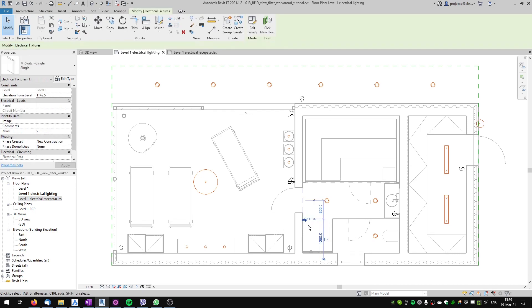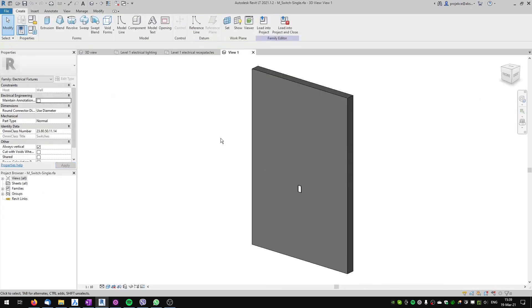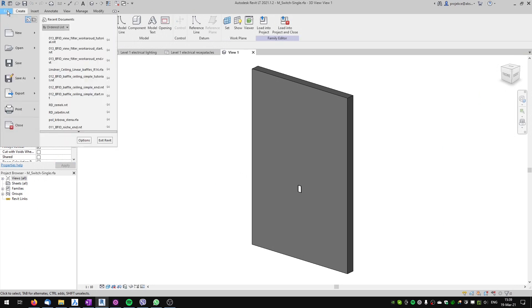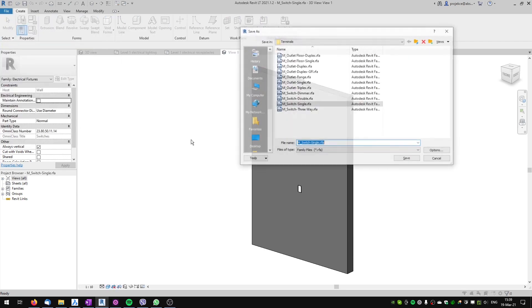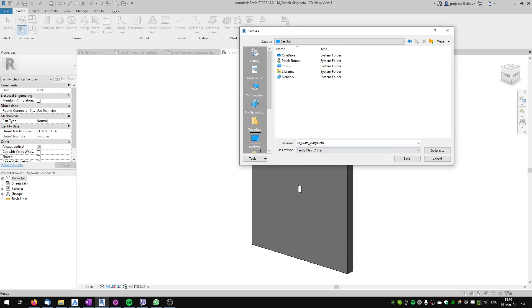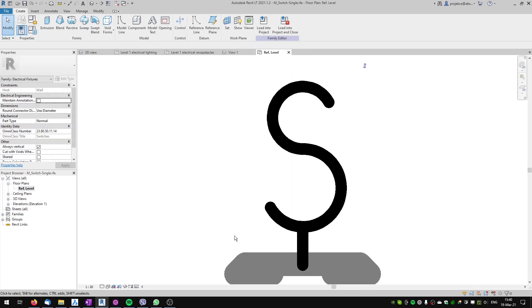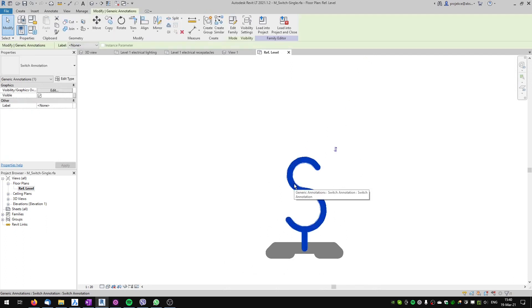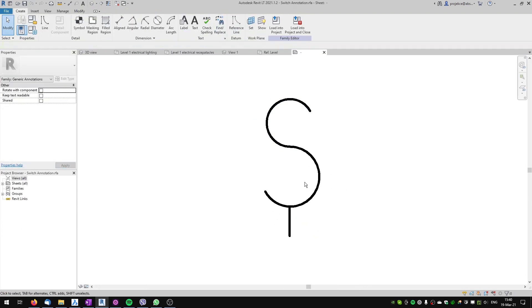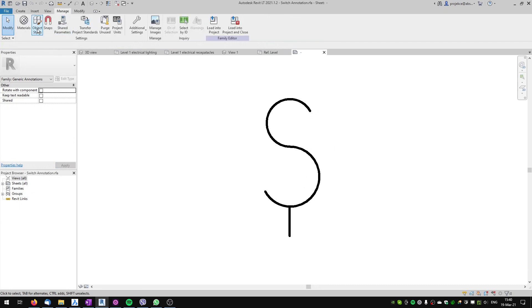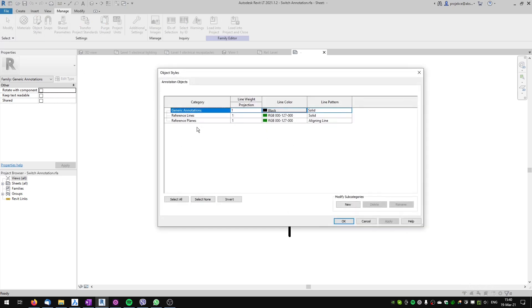To separate the symbols of receptacles and switches we will have to modify the families. First I'll select the electrical switch single and go to Edit Family. So that I don't change my default Revit library family, I'll save this family as a copy to the desktop with the same name. In this switch family I'll go to the floor plan view — here is the symbol, which is a nested family. I'll edit this family and go to Manage, then Object Styles, to create a new generic annotation subcategory.